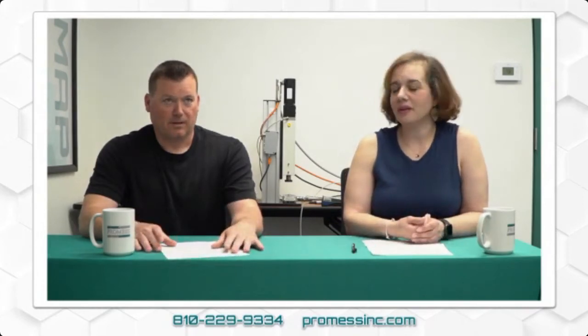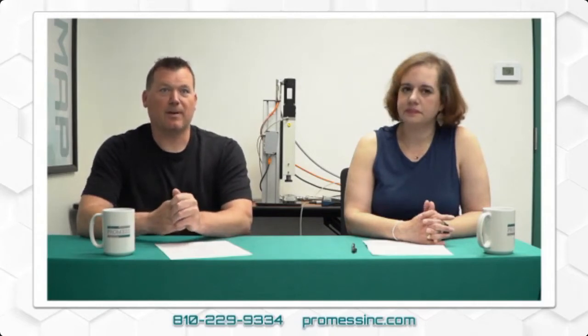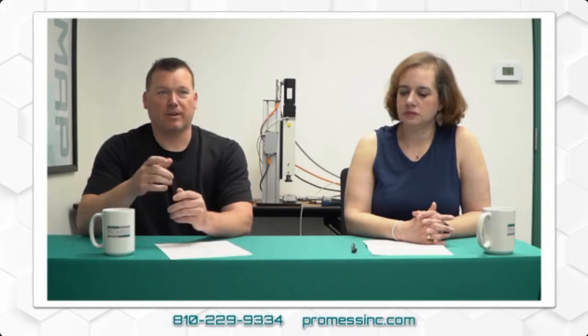So, going back to calibration, because that's what we're here to talk about. Calibrating and verifying are two different things, so I want to clarify a little bit. Calibration is where you're actually comparing the value of the integrated load cell on the system to a certified master load cell and then making an actual change to that measurement so that it matches. That would be an official calibration. A verification is where you compare the two readings. If they're within a tolerance, there is no reason to make an adjustment, and you go on with whatever it needs to do after that point. Those are the two differences. Calibrating is actually making a change to the settings so that it reads correctly. Verifying is simply making a comparison between the two.